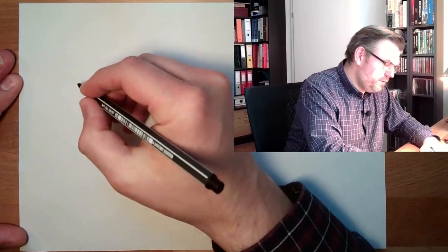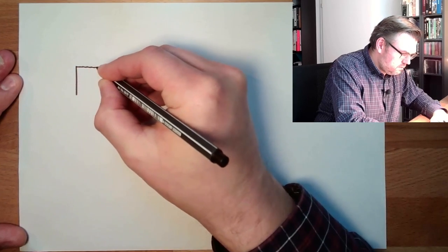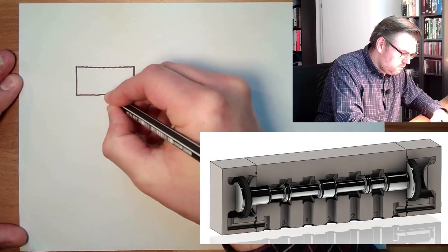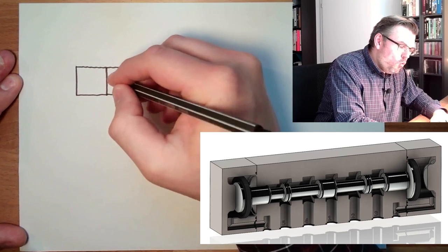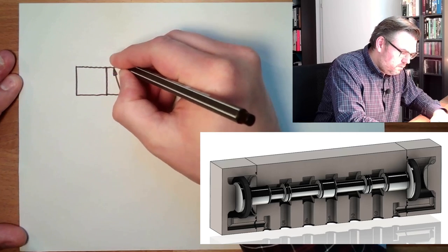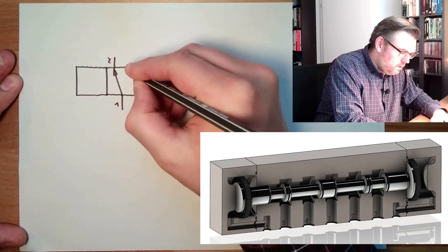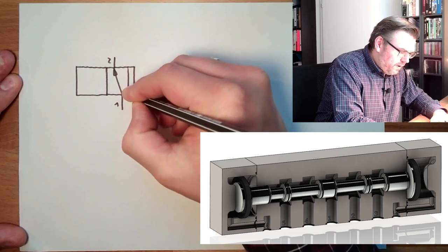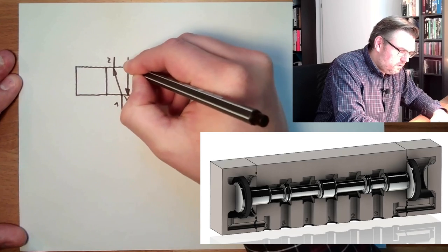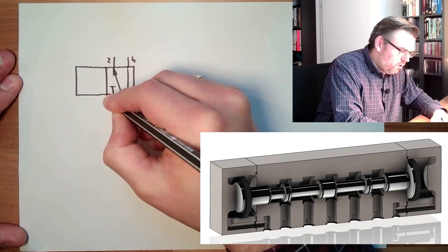Let's come to the variants where we want to talk about the symbols. I will draw the symbols of both of these valves. So we identified this as a 5/2-way valve. So we have two switching positions. One was connected to two. So here's two, here is one. Four was connected to five. Here's five. Here's four. And three was simply blocked.